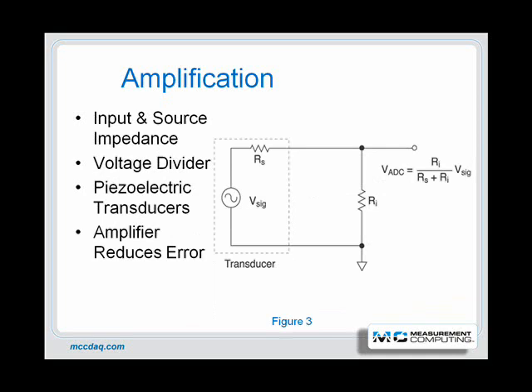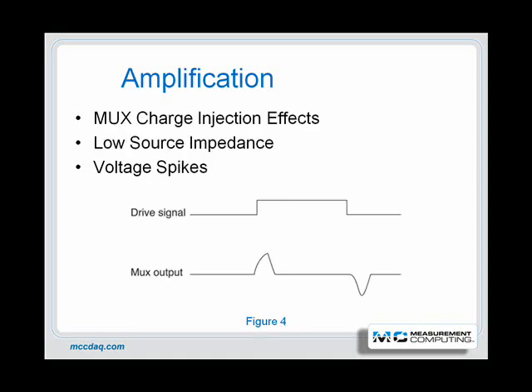This diagram shows how system input impedance and the transducer source impedance combine to form a voltage divider. The divider reduces the amount of voltage the ADC can read. The input impedance of most input channels is 1 megohm or more, so it's usually not a problem when the source impedance is low. But some transducers, like piezoelectric sensors, have high source impedances and should be used with a special charge amplifier. Also, multiplexing can greatly reduce the data acquisition system's effective input impedance.